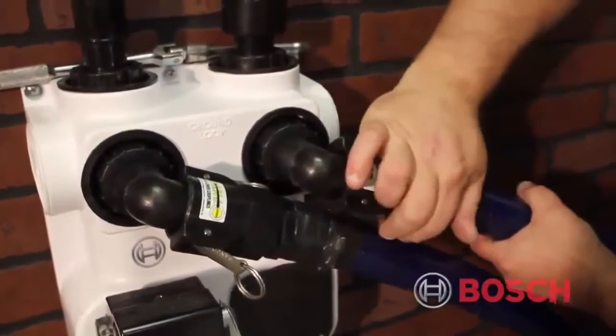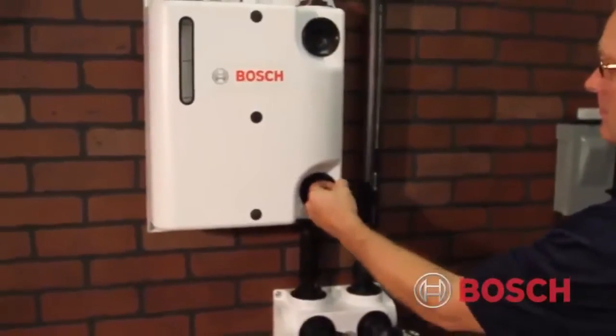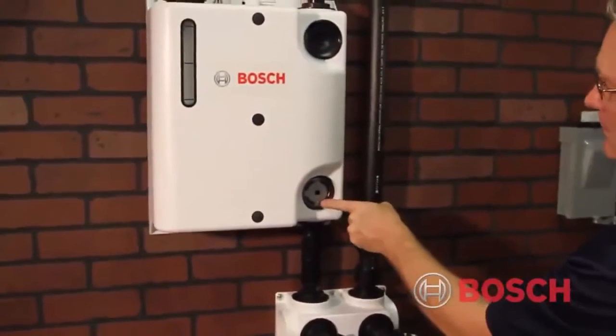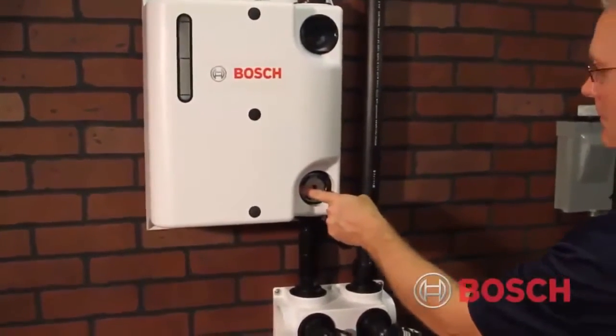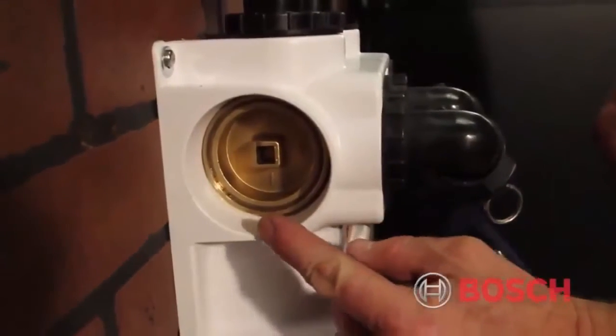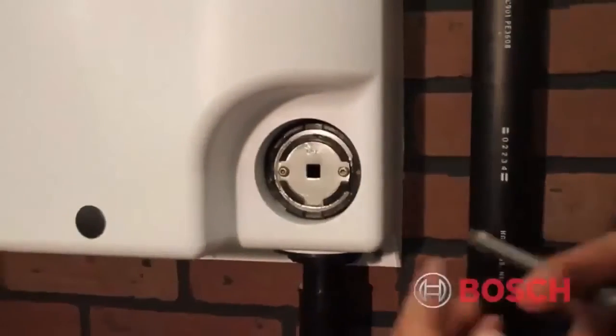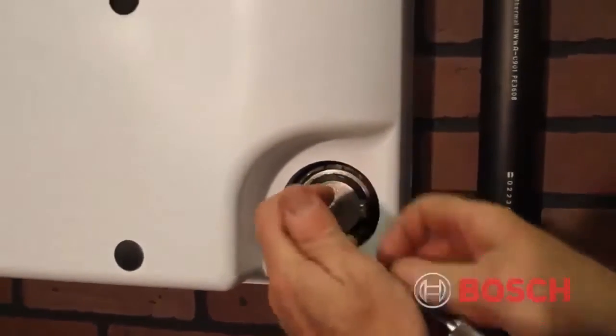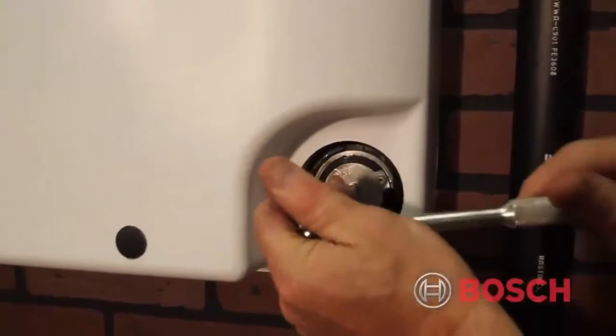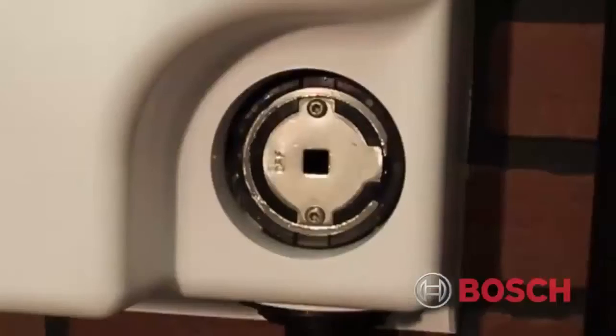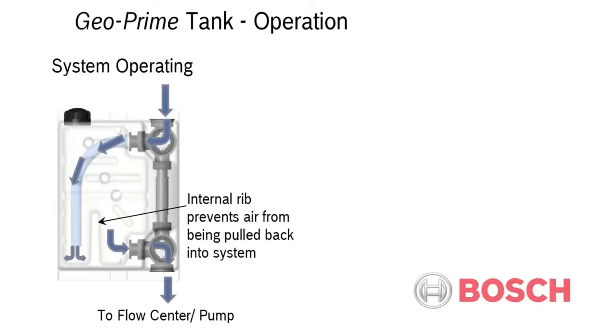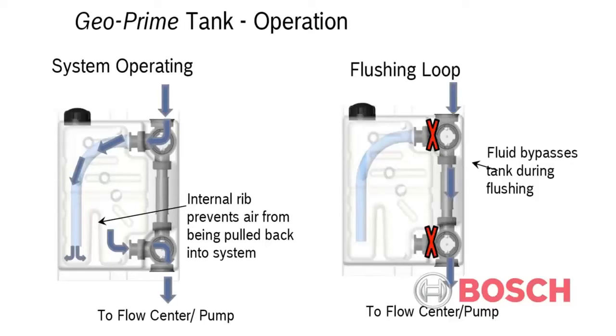In order to properly purge the ground loop, we now have to adjust the position of the factory set three-way valves on both the GeoPrime tank and the FlowLink pump center. Starting with the GeoPrime tank and using a 3/8 inch drive, isolate the prime tank by rotating the three-way valves from the operation position to the bypass position. Adding any sort of water pressure to the GeoPrime tank during commissioning process will void the GeoPrime warranty.